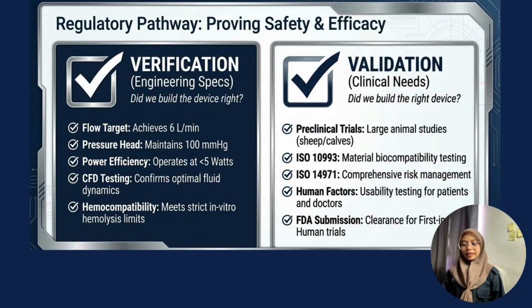I will explain the regulatory pathway for the AeroHeart LVAD, specifically the difference between verification and validation in proving the safety and efficacy of the device. So verification focuses on engineering specification, which in simple terms answers the question, did we build the device right? We have 5 points, the first being the flow target. The AeroHeart LVAD successfully achieved a blood flow rate of 6 liters per minute, which matches the normal cardiac output required for adult circulation.